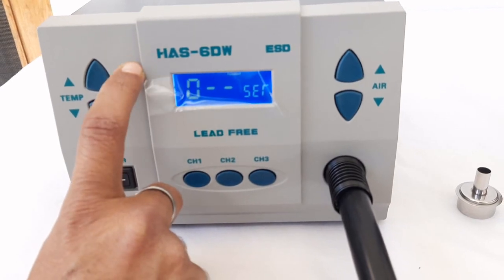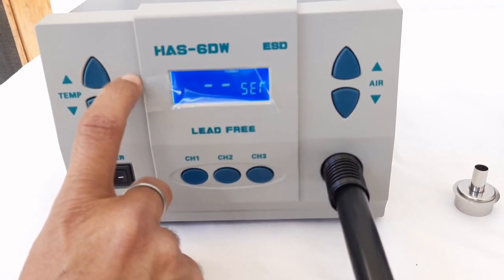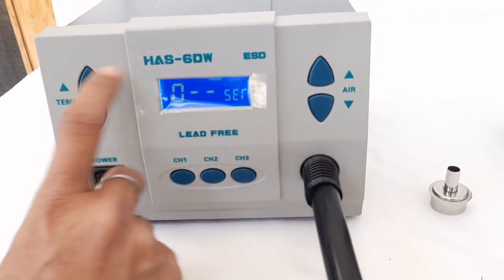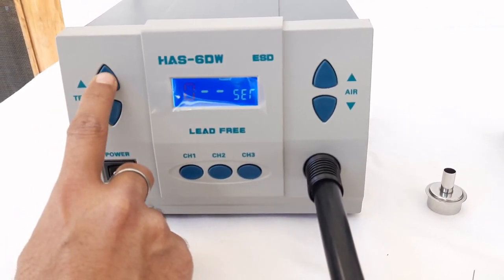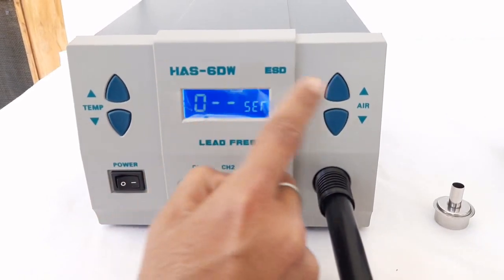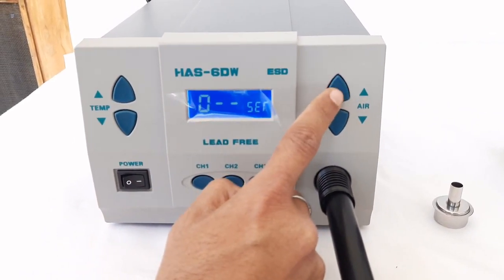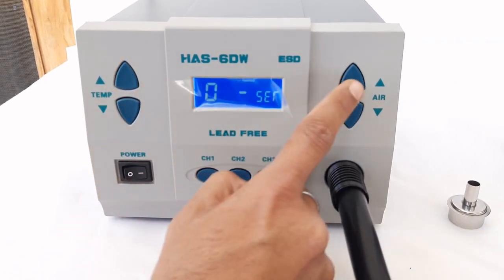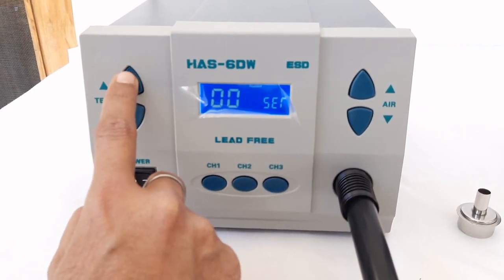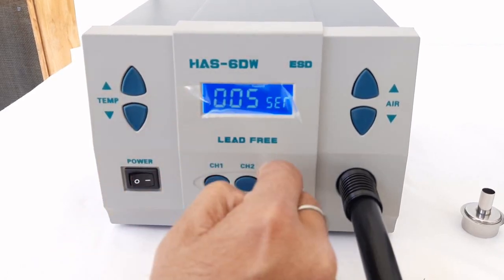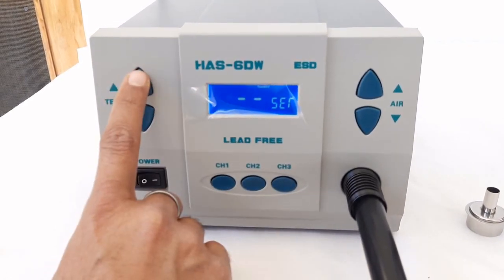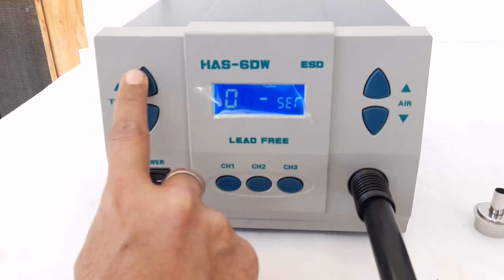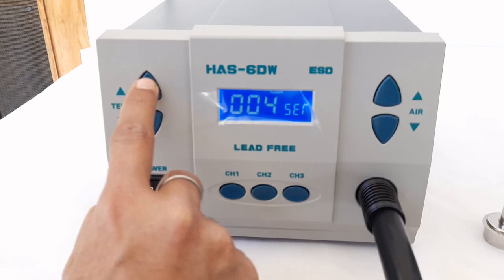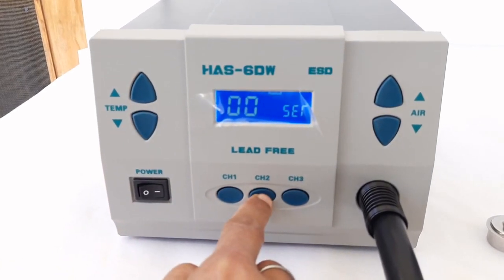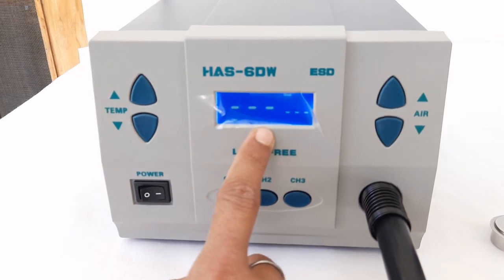All we need to do is use this up temperature or down temperature key to select a favorite password. Like if we want to use 005 as our password, we need to select this 0 first, then to move to the next step we need to press this up side air button, then again 0, again this up button, and select 5, then press channel 2 once again and repeat the same process. And then press channel 2. Now the password has been saved. The password we selected was 005, so the same password has been saved.